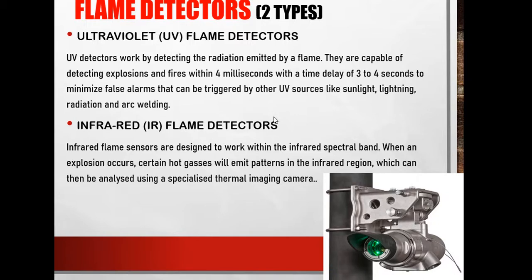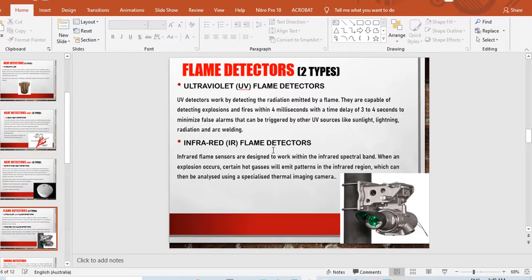Okay, then we go to flame detectors. Now, don't get confused about heat detectors and flame detectors, because we use all of them. It's all a combined effort, because we don't want spurious trips. For a lot of these detectors, there's what we call voting: one out of two, two out of two, two out of three. A fusible plug might go off and initiate an alarm if it's just one, but it may not be a real fire scenario. It might be a one-off, and then you have the alarm going off and everyone's getting worried. So they have voting mechanisms so that two have to go off before the alarm goes off. If one goes off, it doesn't initiate anything, or it might just initiate a very low alarm. But when two go off, that means this is confirmed fire detection.